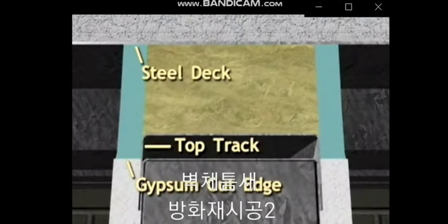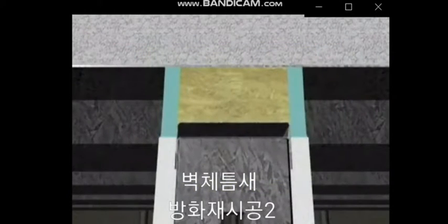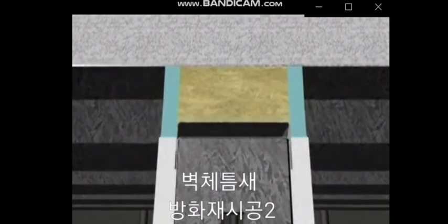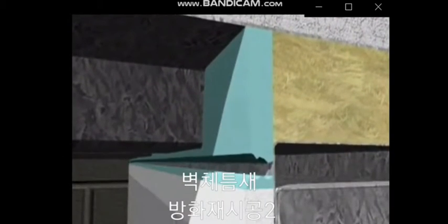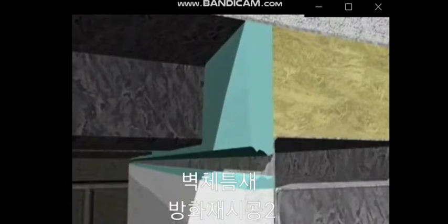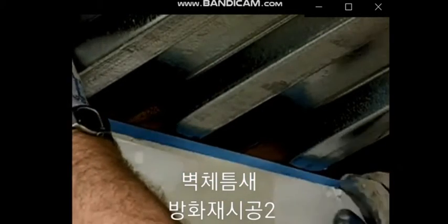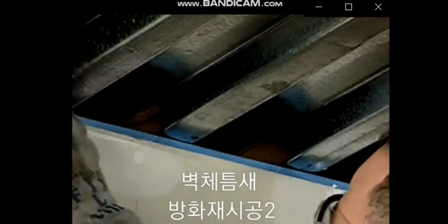on the bottom. When adhesion occurs only on two sides, the joint moves freely and the sealant moves with it. But when the sealant bonds to a third side in a joint, the sealant becomes glued shut and will be torn apart when the joint opens.